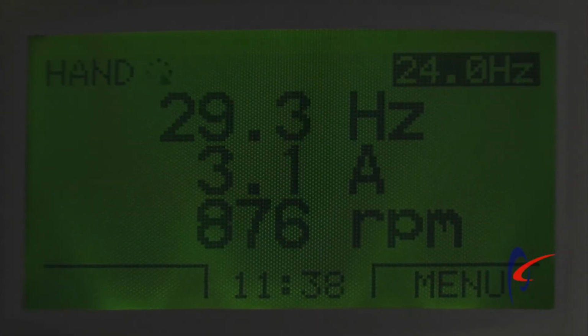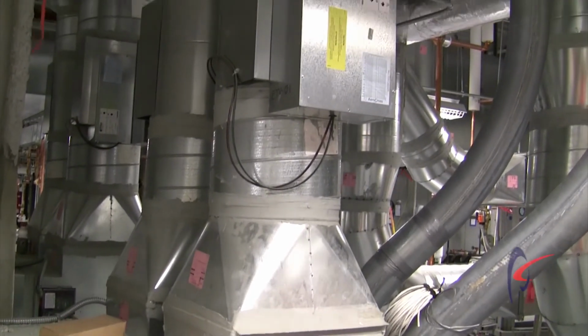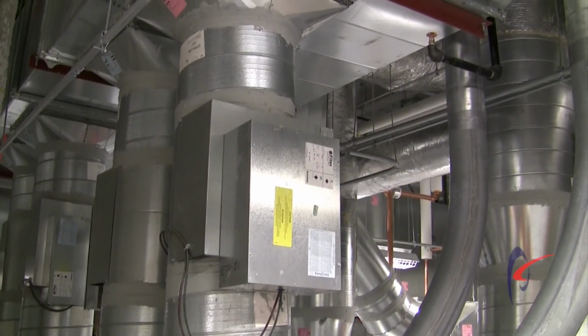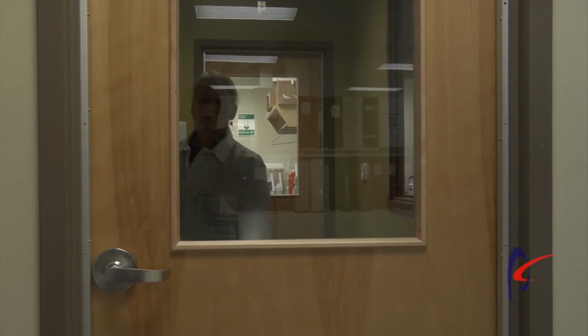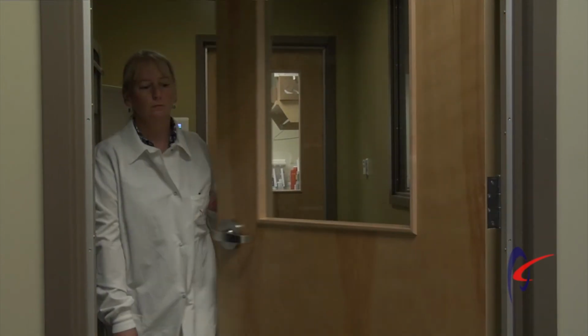The third problem that can happen with pressure transducers and cross-flow sensors is drift. What can happen over a year, over 2 years, is the general accuracy of these devices can change. The more you're trying to turn down that airflow, the more accurately you want to measure that lower airflow. If these devices have drifted over time and not been recalibrated, this can compromise the pressurization of your spaces.